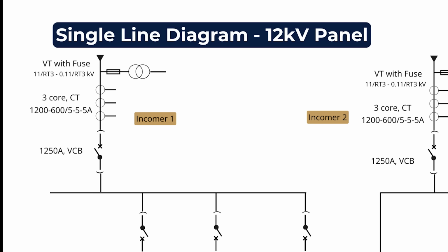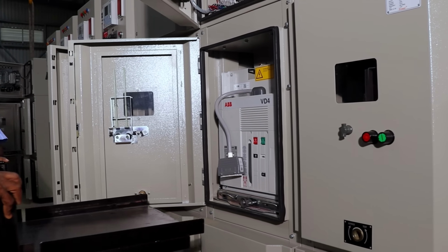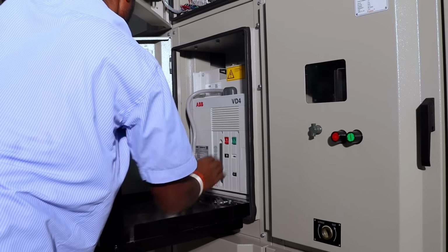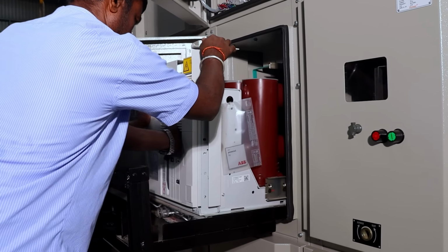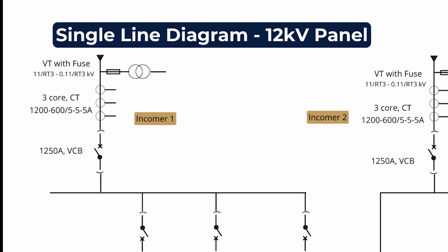And then the main part of the panel, that is the circuit breaker. Here we are using a 1250 amps vacuum circuit breaker. Now when you see this kind of symbol where we have the brackets, it means the breaker is withdrawable. You can remove the breaker when you are, let's say, carrying out a maintenance activity or you want to swap it with another panel. You can take out the breaker completely from the panel and carry out the maintenance and all the other things that are needed. Now the advantage with this arrangement is that we don't need a dedicated disconnector for this, because IEC says when you remove the breaker we get the isolating distance that we need. So that's the advantage. I'll show you the rack in rack out operation as well.